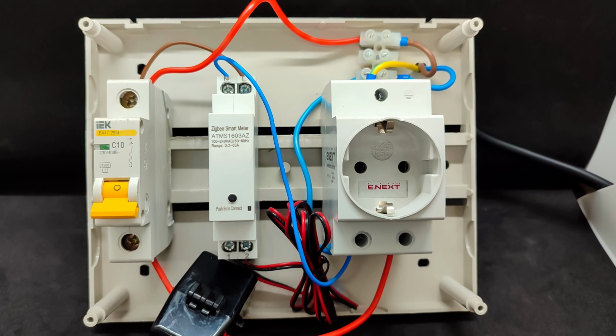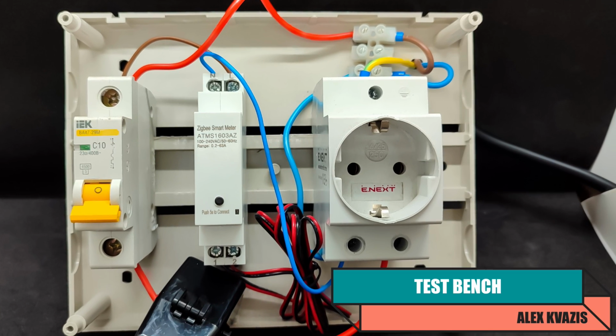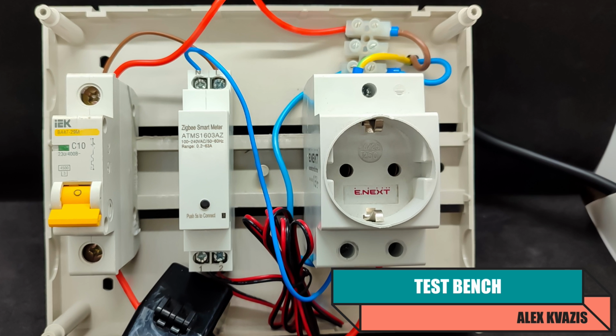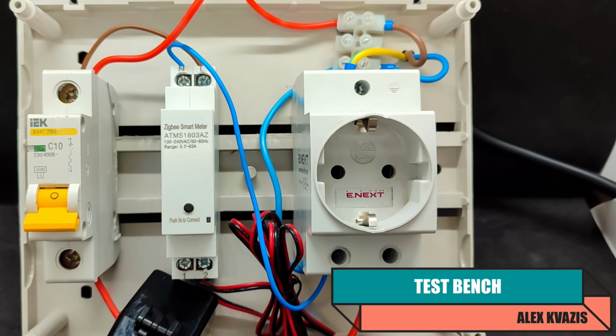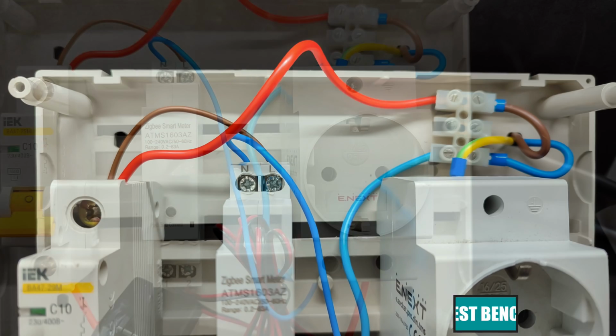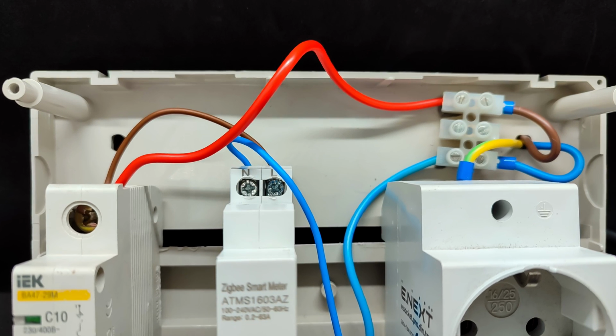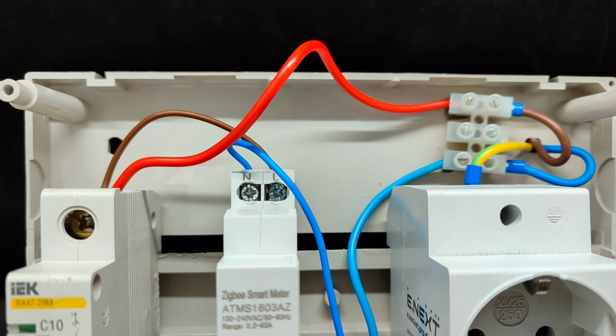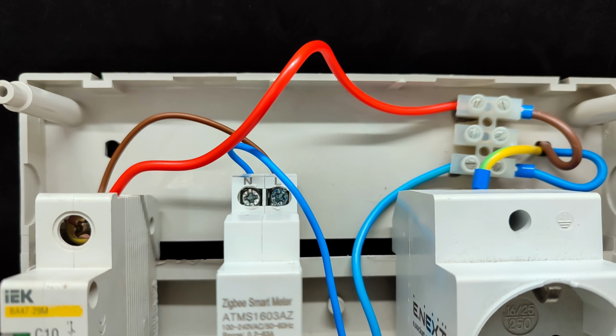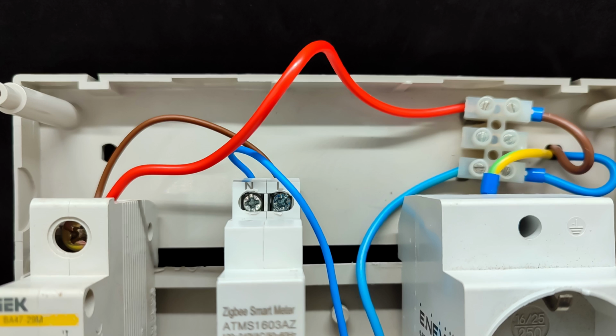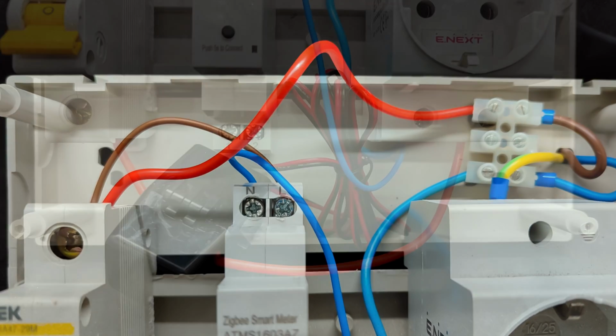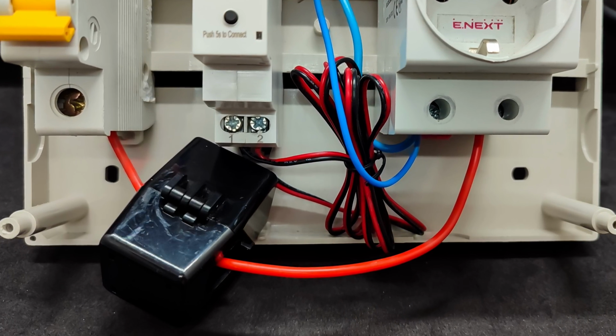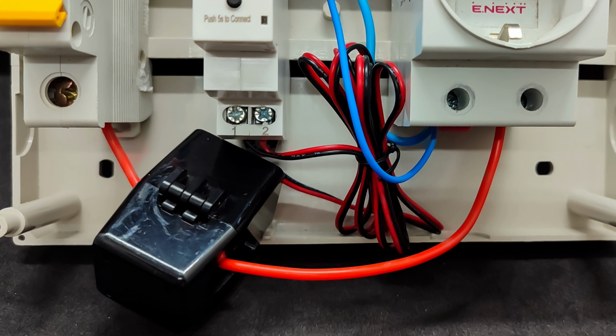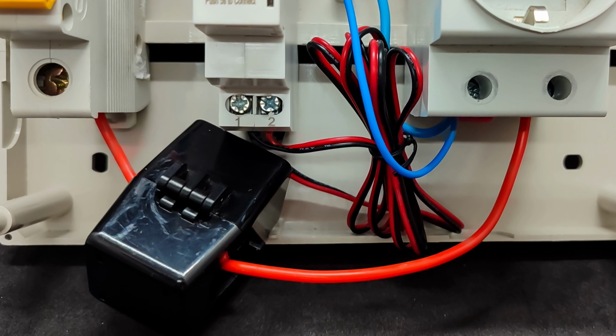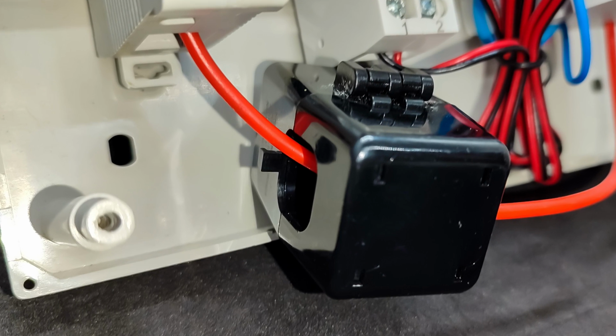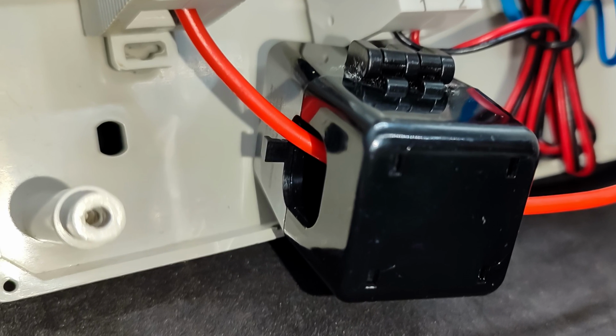For testing, I assembled a small bench setup. The neutral line, blue wire, goes directly to the socket, where the load will be connected, into the N terminal of the energy monitor. The phase from the mains, red wire, goes to the circuit breaker. From the same terminal, directly, a thin brown wire runs to the L terminal of the energy monitor, ensuring it is constantly powered. The phase, red wire, then exits the circuit breaker and goes to the socket where the load will be connected. The current transformer is clamped around this wire, ensuring the arrow points from the breaker to the socket.